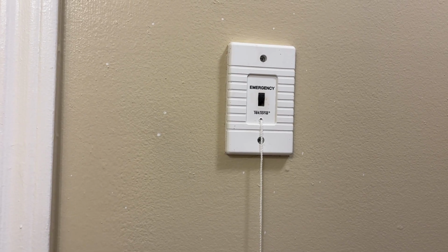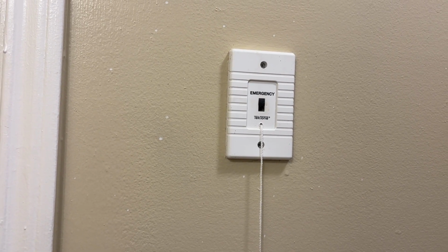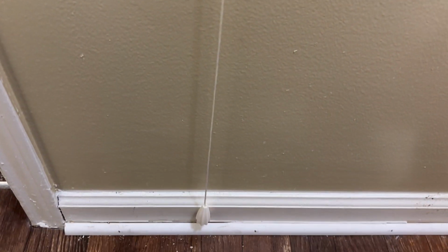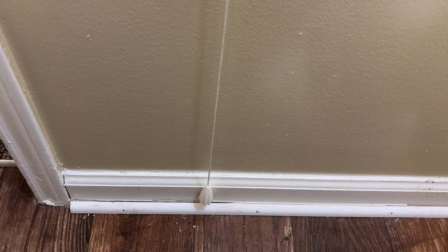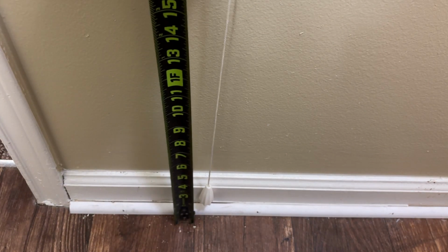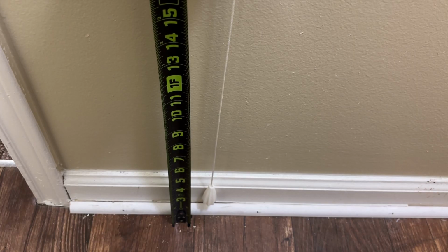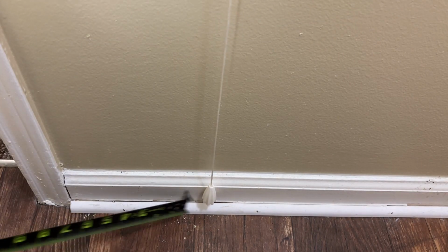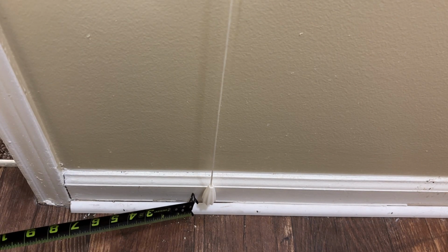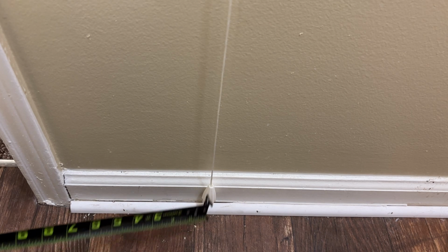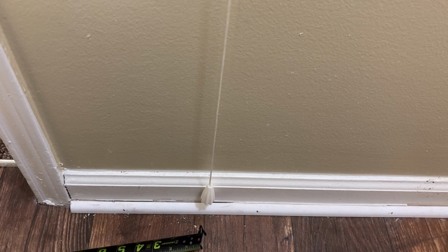Testing an emergency pull cord system. The bottom of the pull cord can be no higher than 6 inches. If the bottom is higher than 6 inches, it needs to be extended or the pull cord needs to be replaced. The easiest way to do this is to mount it in the center of the trim. The emergency pull cord can also not touch the floor.